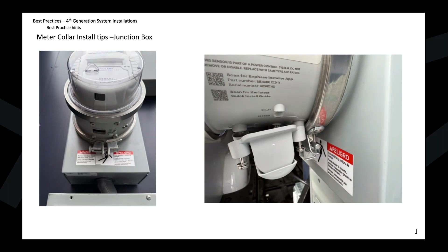Same thing kind of goes for when you're sealing the meter collar. We're using a screw type seal ring. We want to make sure that we're grabbing both the lip of the meter collar as well as the actual meter pan itself. So there's 2 lips that you've got to grab, and then when you tighten that screw type ring down, it secures it really nicely. If you kind of position yourself on the right, taken from the left picture, gradually move yourself to the right side of it. You can see here they completely missed the lip of that actual meter pan. Again, not securing it correctly. If somebody came up and, say, a kid grabbed onto it, well, that's probably going to pull straight down.